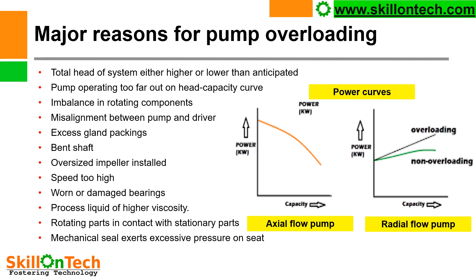Major reasons for pump overloading include: total head of system either higher or lower than anticipated; pump operating too far out on the head-capacity curve; imbalance in rotating components; misalignment between pump and driver; excess gland packings — if the pump stuffing box is filled with excessive gland packings, that will increase friction and cause the motor to draw more current; oversized impeller installed; speed too high; worn or damaged bearings; process liquid of higher viscosity; rotating parts in contact with stationary parts; and mechanical seal exerting excessive pressure on seat.